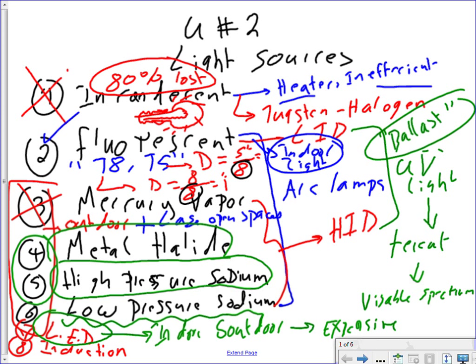If you look at page 21, there is the warm-up for high pressure sodium. It needs 5 minutes to come up to speed. Can you see that on page 21, figure 2.11? It starts at zero and goes all the way up. After 5 to 6 minutes, it comes up to full brightness. That's a disadvantage, the longer warm-up time. Look at the current at the top. There's an inrush current, up to almost 130%. It will draw more current when you start it, like a starting current.